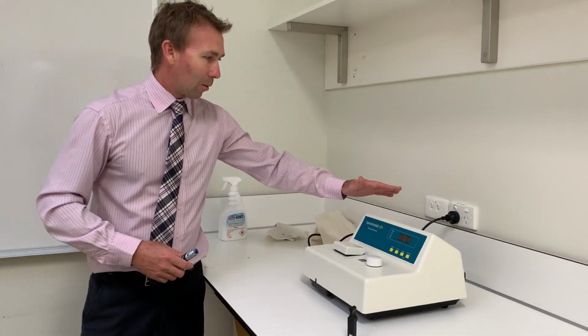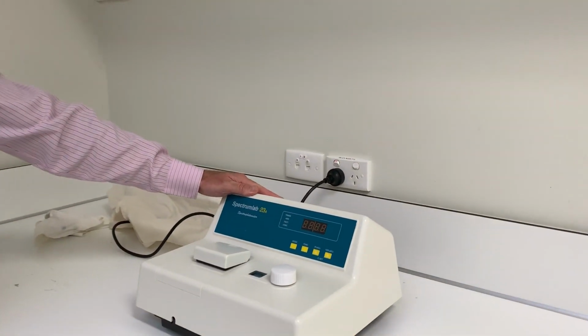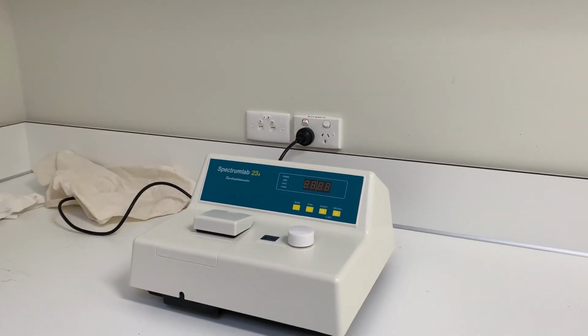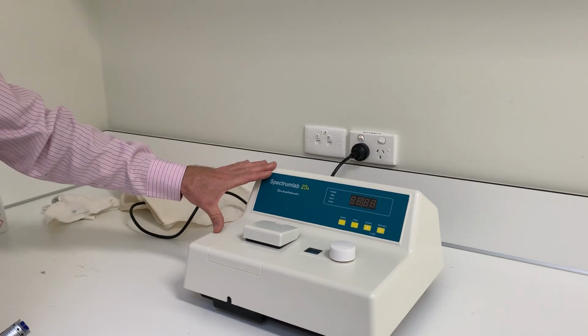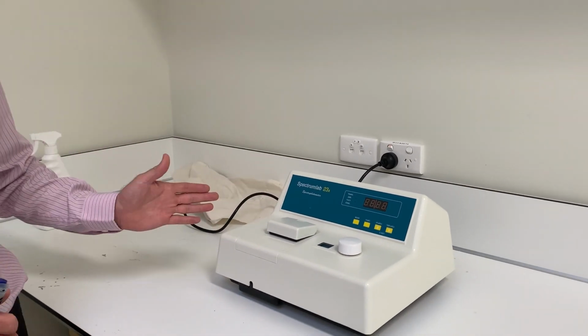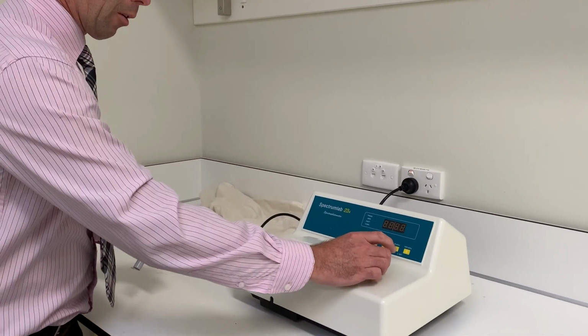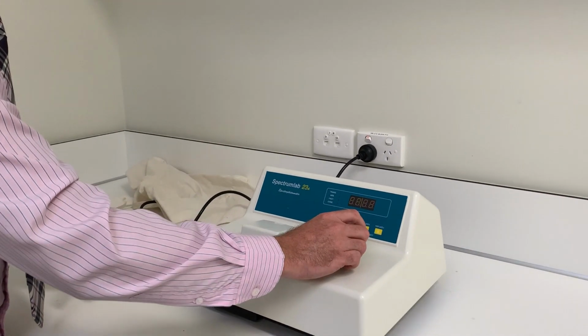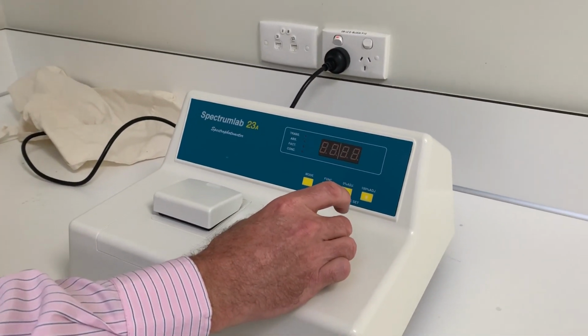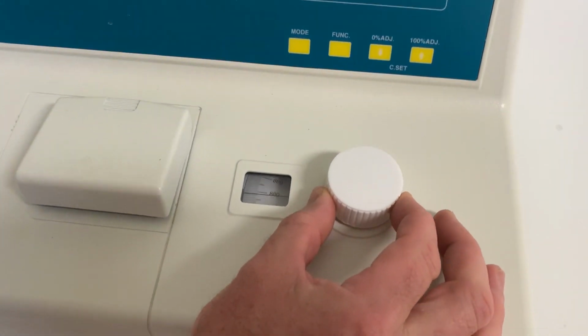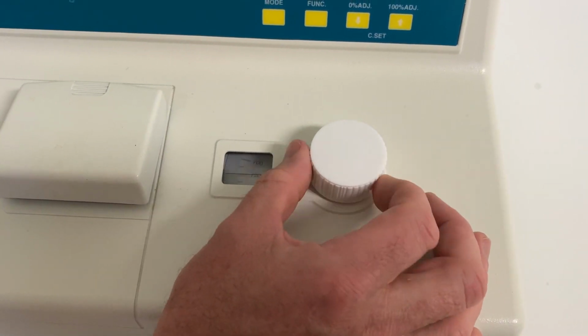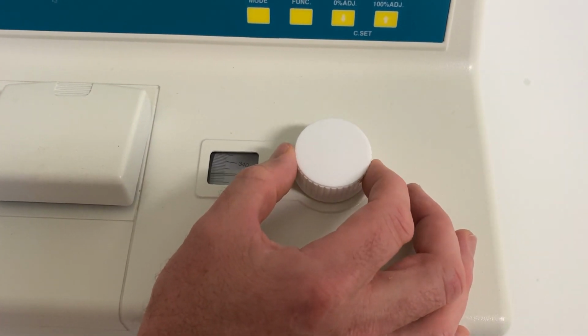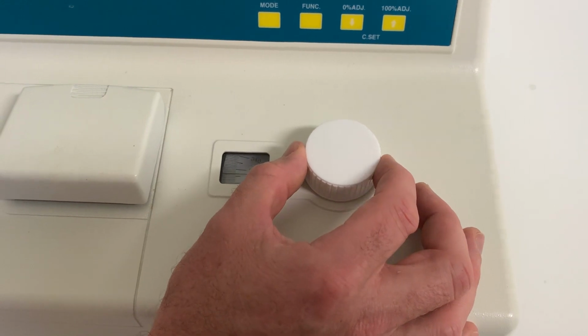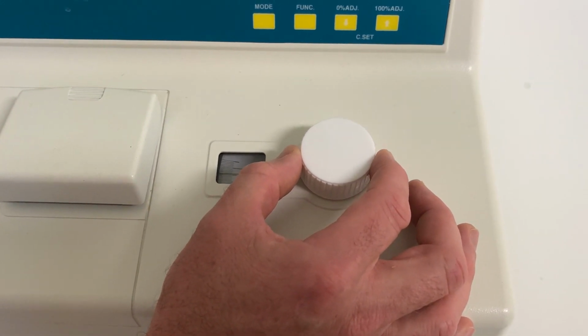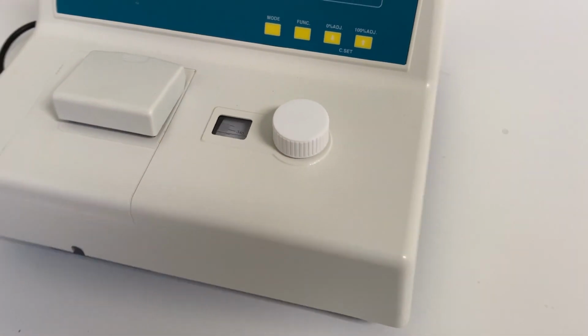So the first thing, we call this a UV vis spectrometer, but this one here doesn't actually go into the UV range, so you're basically looking at anything from around 800 nanometers, which you can see here on the dial. It says a little bit higher, but it's probably up around 900, and it will go all the way down, and it says here down to about 340, but you're probably lucky to find anything decent below around 350.